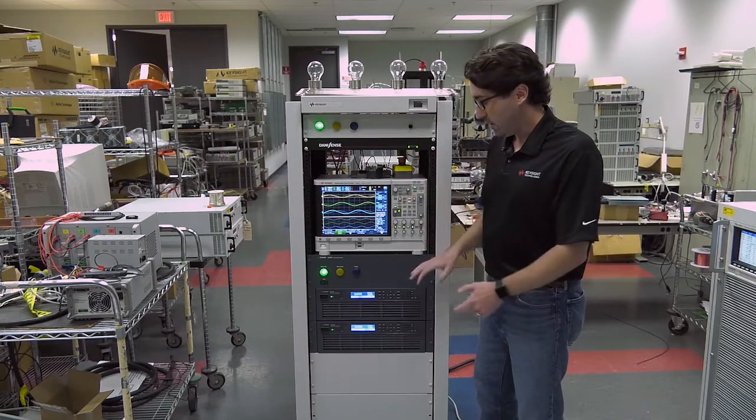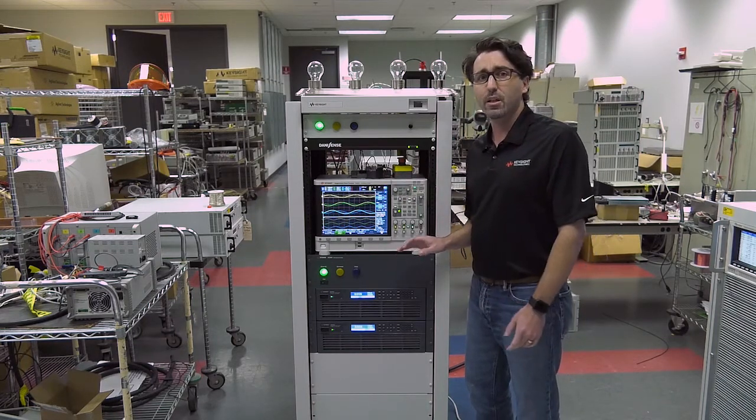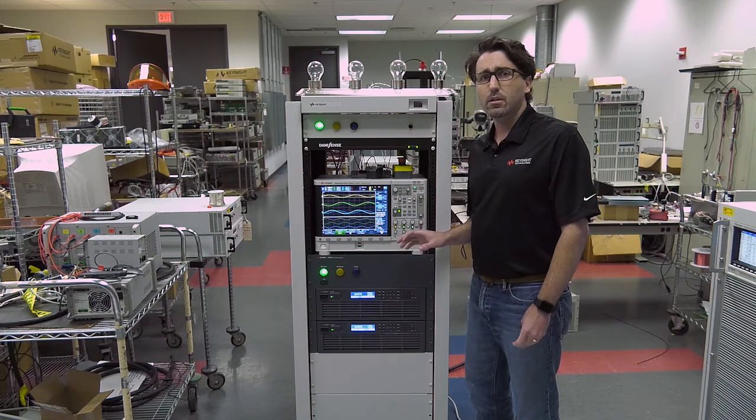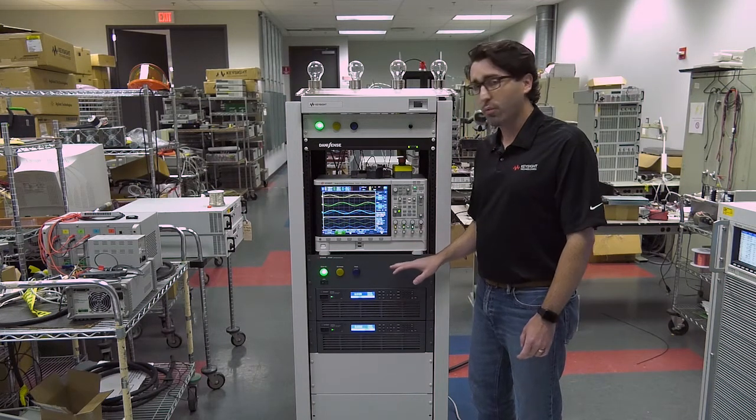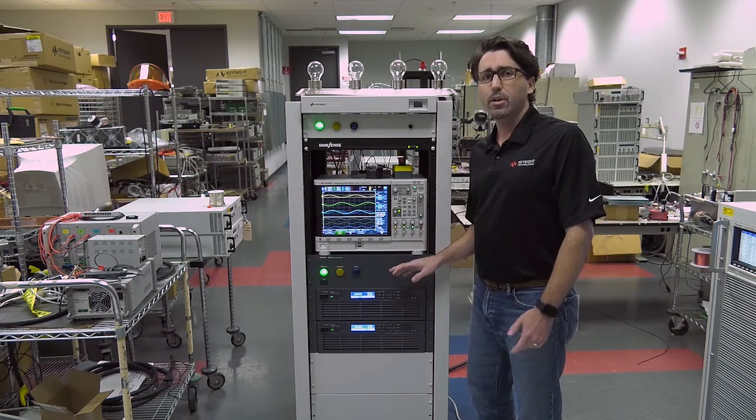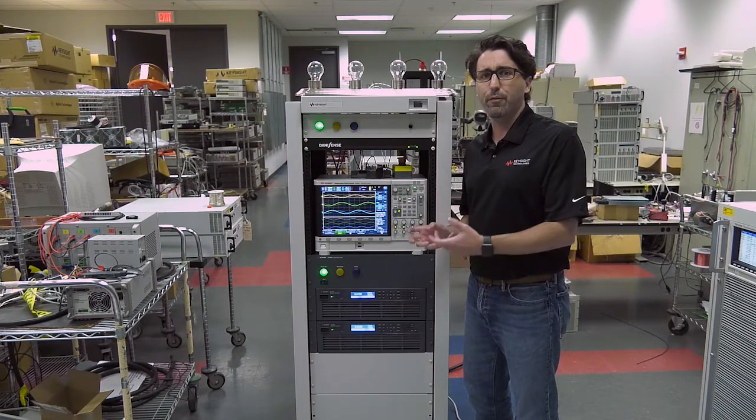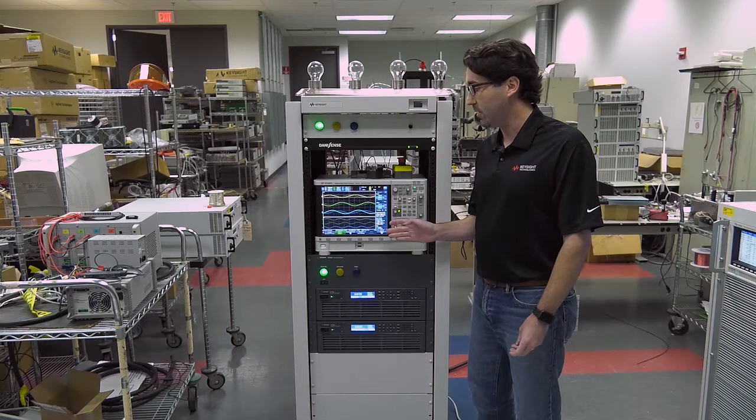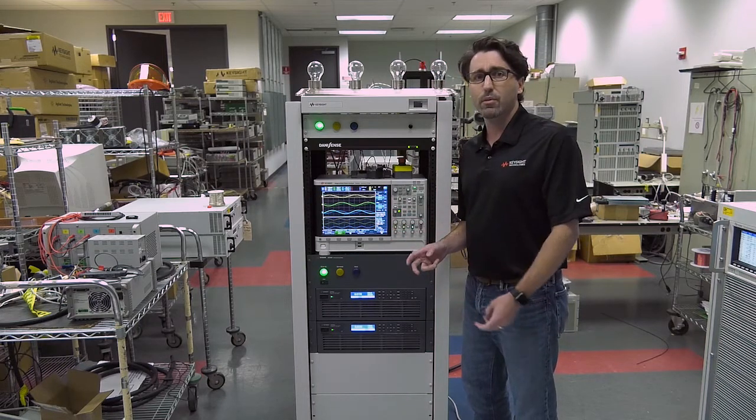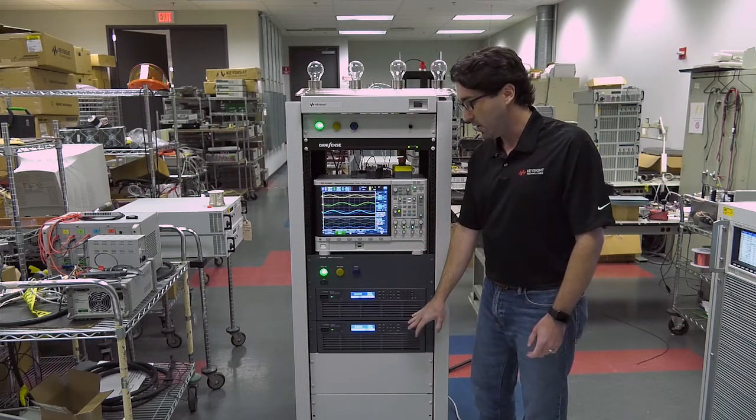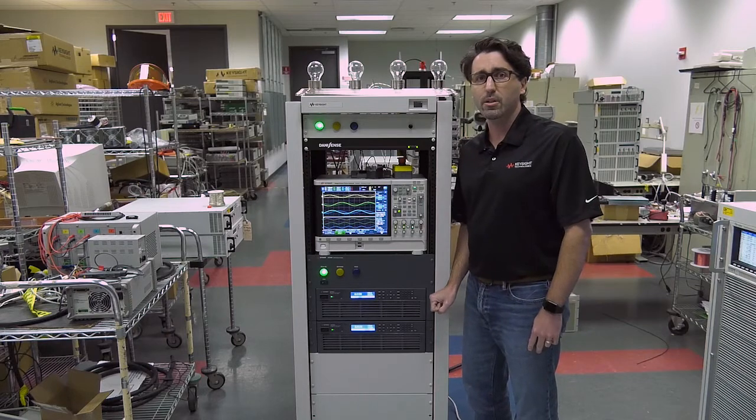Now today we've hooked this system up to a very clean AC source in order to provide the three-phase AC input, because regular grids can have some voltage noise on them that would affect the measurement in this system. So you need to do this in a laboratory environment to show how clean the RP7900 regenerates back to the grid.